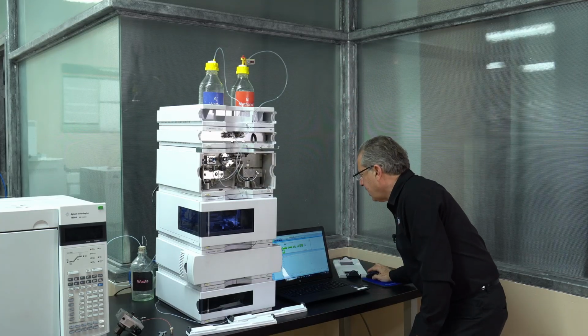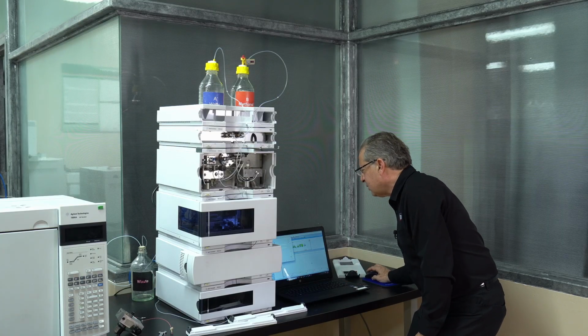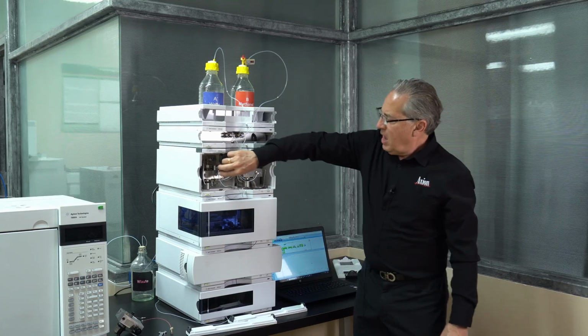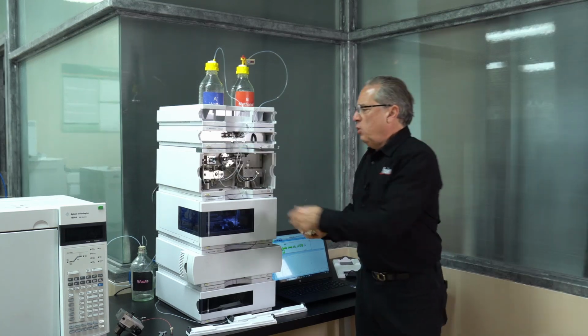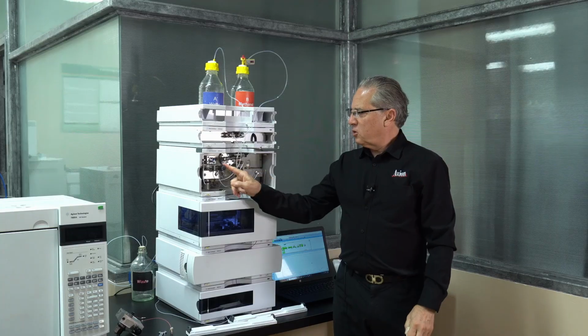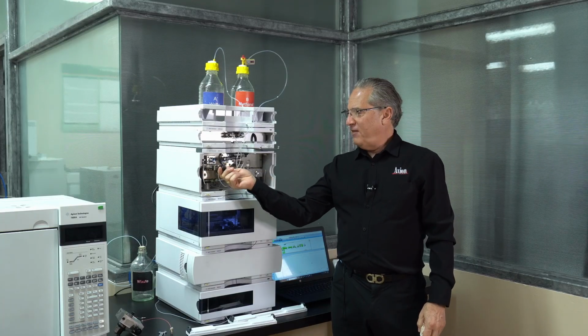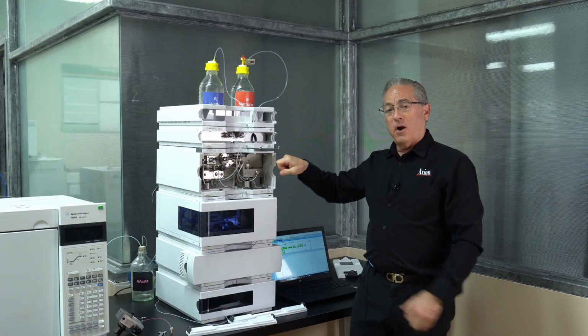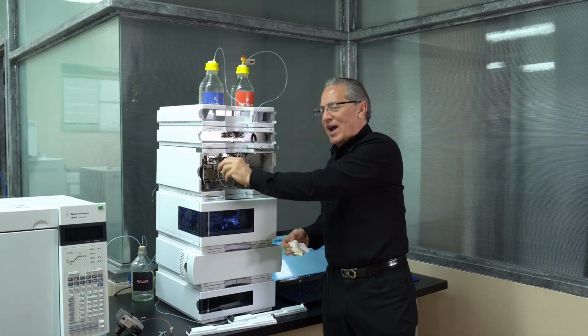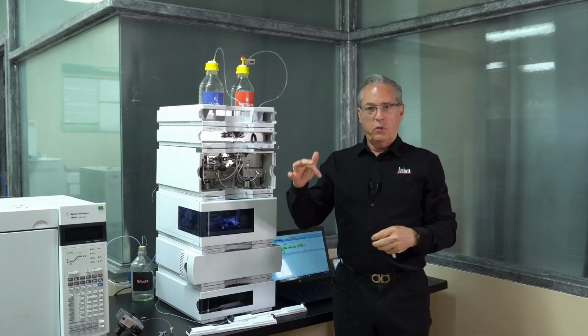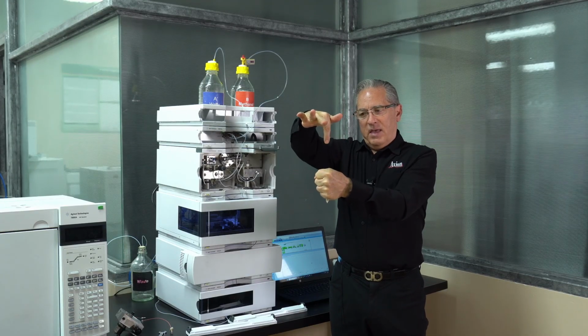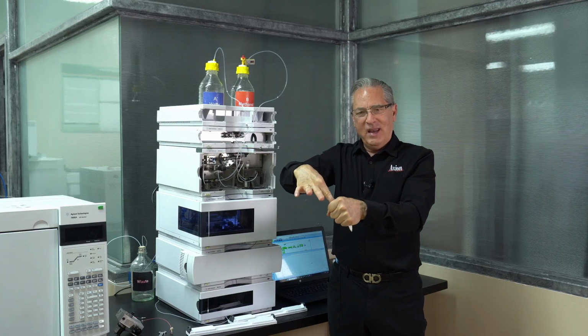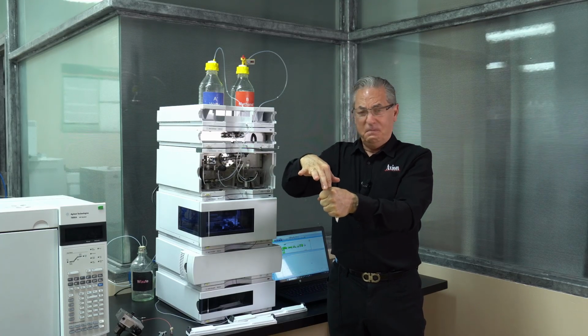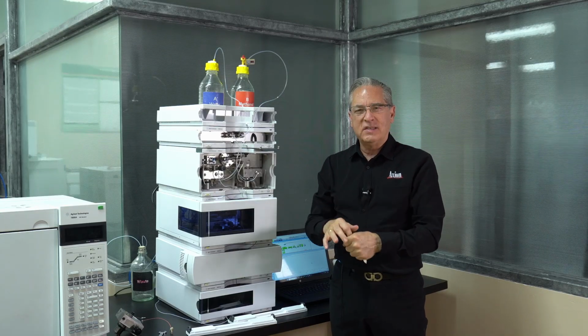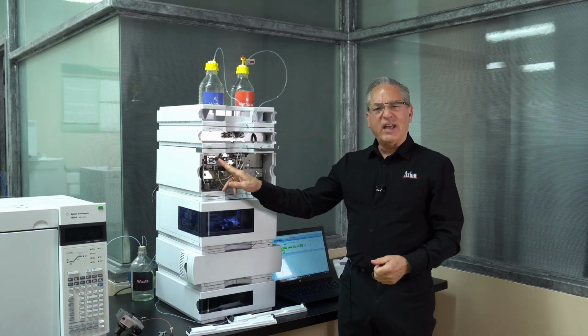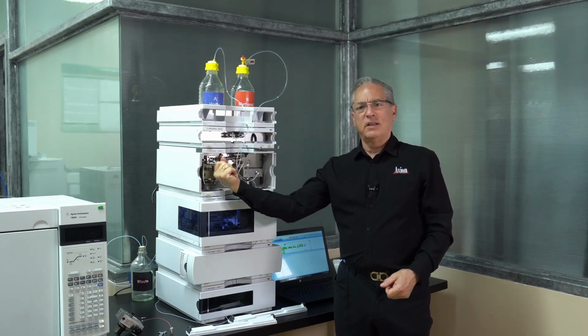Once I've done that, I'll come back here and I'll set the flow rate back to 2 mils a minute, which is what I'm using for this method. I will close the purge valve. Remember with purge valves, they don't need to be monster tight. There's a reason why they gave you a round valve. If Agilent wanted you to crank on this, they would have put a sidearm on so you could do that. The fact that it's round means it's a needle valve. Needle valves, real simple operation. The needle is up and it's open, the needle's in the seat and it's closed. Well, if you tighten it, then you're just pushing the needle further into the seat. You're not making it tighter, you're actually deforming the seat. Eventually it's going to start to leak. So be careful not to over tighten this. It should be snug, but you don't have to get a wrench or anything to tighten this up.